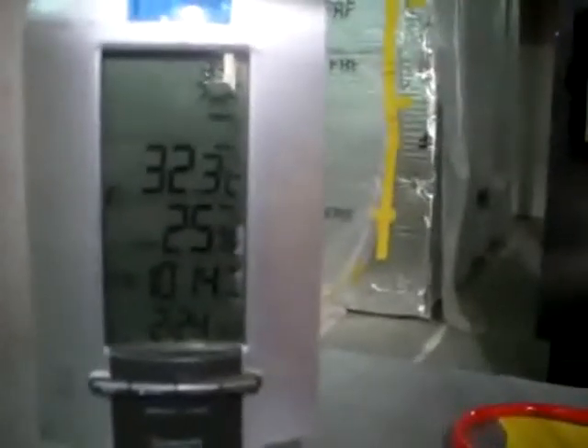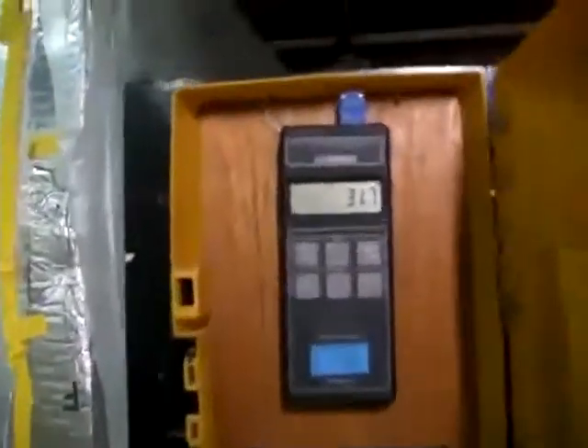We also use a calibrated timer to record timings between each reading. We also use the weather station to measure the ambient temperature, relative humidity, barometric pressure. We have developed an Excel sheet where we have inputted the formulas from BS 848 to manually calculate the flow reading from the conical inlet nozzle. We also use a digital thermometer to measure the temperature inside the chamber.